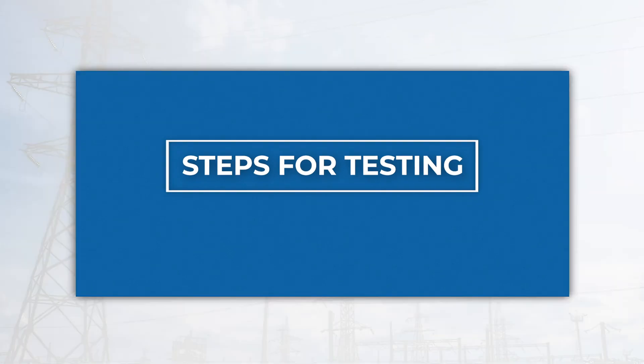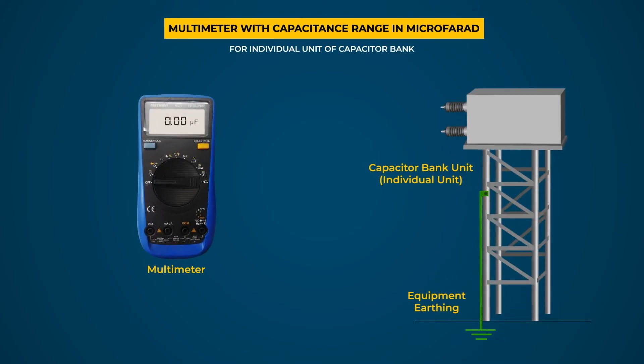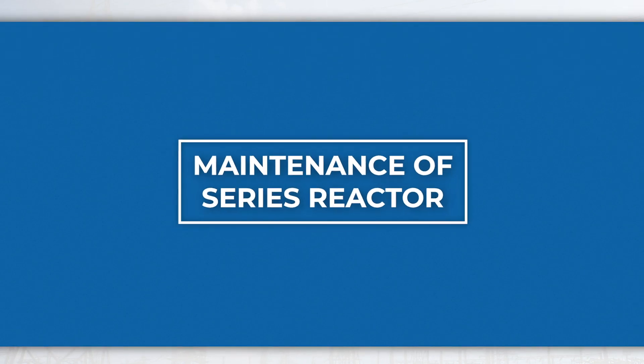To measure the capacitance of an individual capacitor unit, move the selector switch of the multimeter to the microfarad range on the capacitance marking. Connect the capacitance terminal of the multimeter to one terminal of the capacitor unit and the common terminal to the other terminal through leads. The multimeter display shows the measured capacitance value. Record the value and compare with the earlier record or recommended value; if found beyond permissible limit, investigate and rectify the issue.